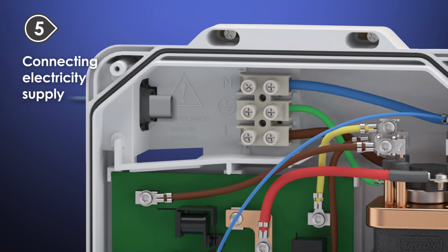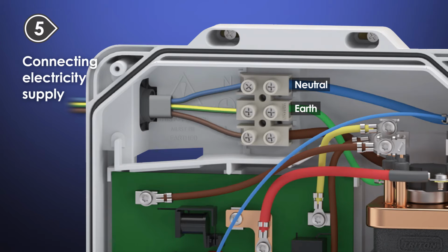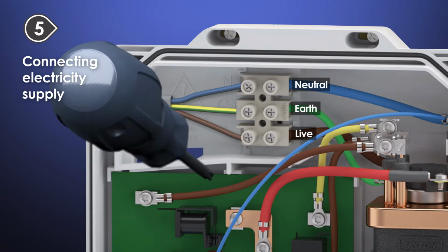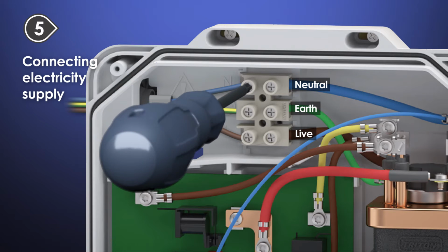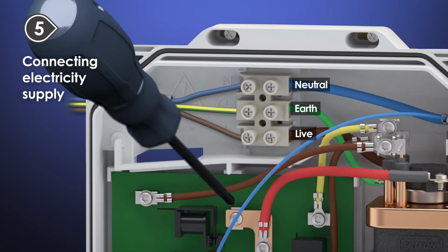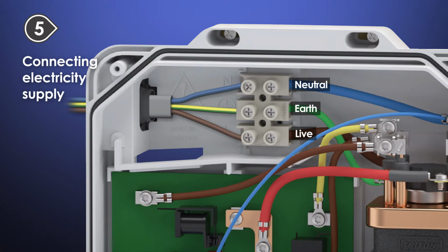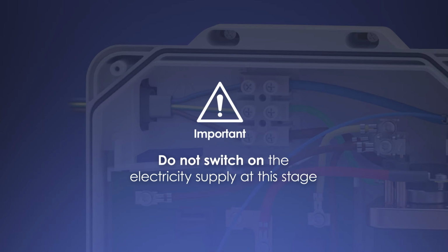To connect the electric supply, route the electricity supply cable through the cable entry grommet and into the Tri-Hub. Then insert the conductors into the relevant positions on the terminal block. Double check that the earth conductor is sleeved and that the outer sheath of any conductor is stripped to a minimum. Tighten the terminal block screws fully and make sure that none of the cable insulation is trapped underneath them. If you have any loose connections, it can result in the cable overheating. Make sure you don't switch on the electricity supply to the Tri-Hub at this stage.